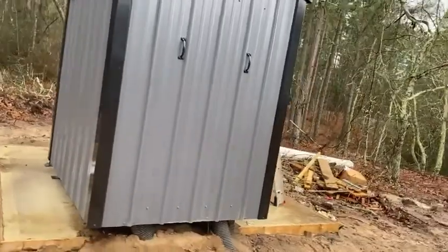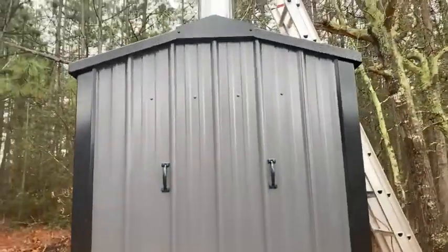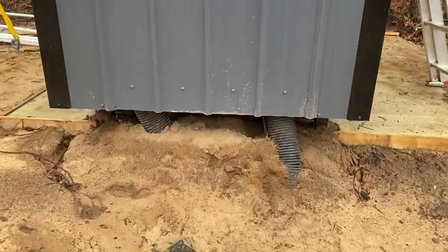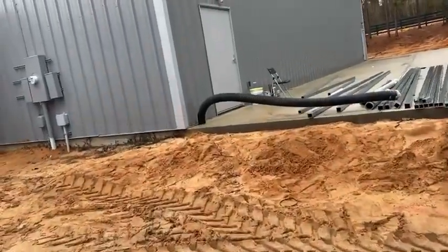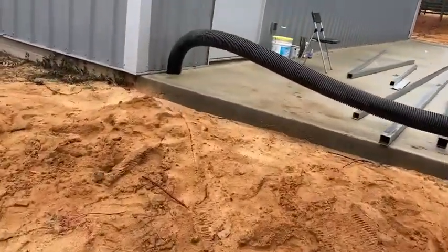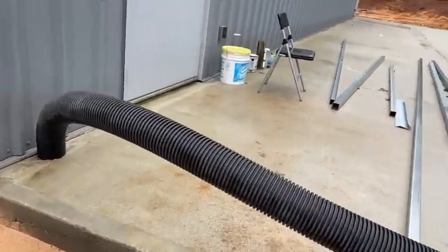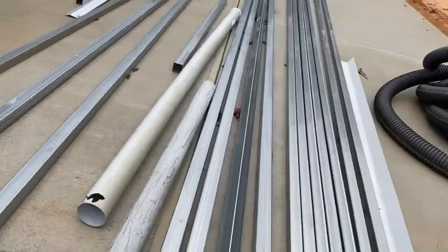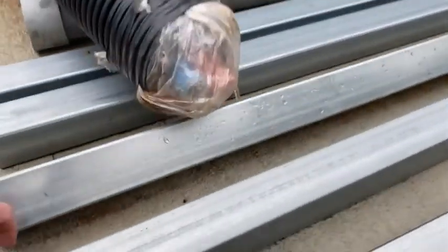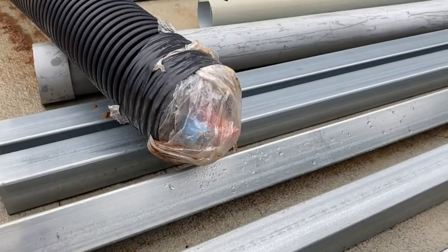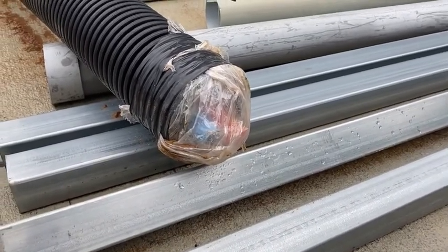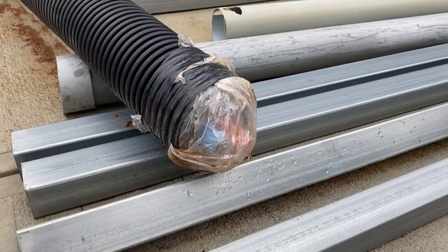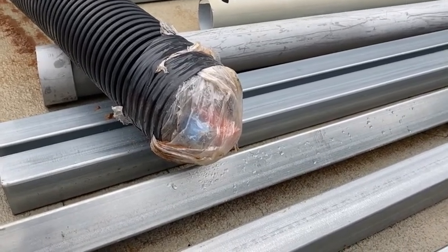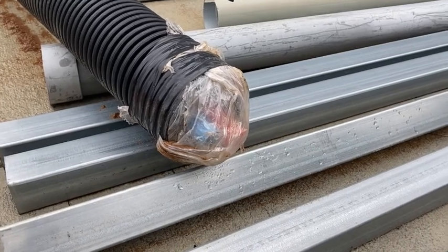I'm going to show you now how it goes from the actual stove over to the building. You can see we come out the bottom of the stove, we trenched over, and we did this before we poured our slab, but we just stubbed up right through the slab. This looks like a 6-inch really well insulated pipe. I think that's really the key to not losing too much heat as your water goes to the heater or the heat exchanger, and then returns to the heater. You want to keep that as insulated as possible to minimize heat loss, so it's less work for the stove to do.